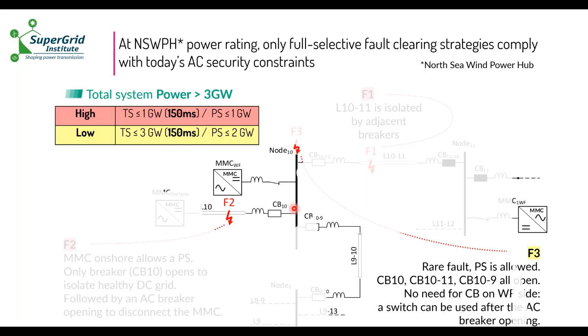For that case, that's why it's F1, and for case F3, it's a busbar fault. It's less probable, so you can't afford to disconnect the adjacent system, which goes through this breaker. So you need to put a breaker there to be selective. But for this single MMC, whenever there's a fault in the busbar, you can afford to lose it, since you're not losing more than 2 gigawatts, and it's connecting a wind farm. So you don't need a breaker there.